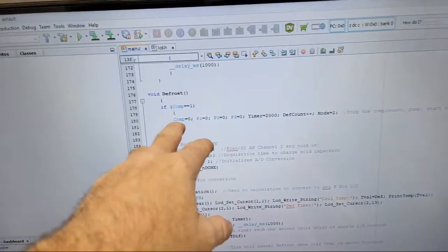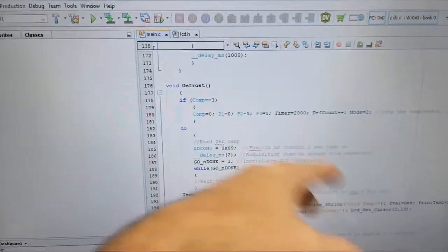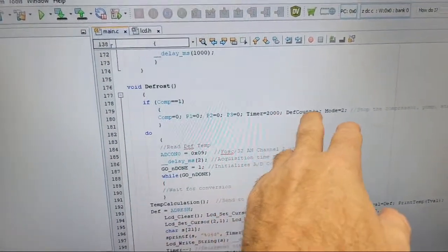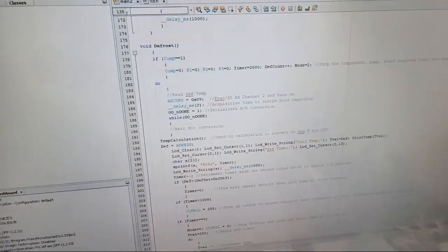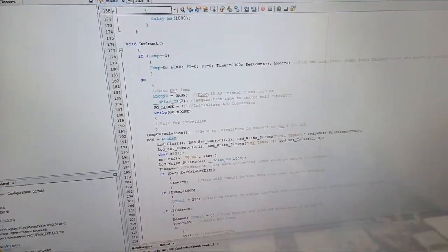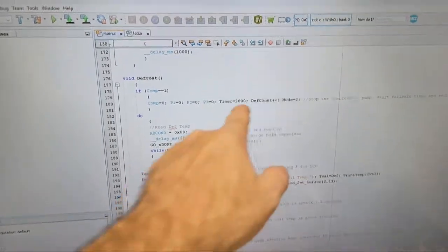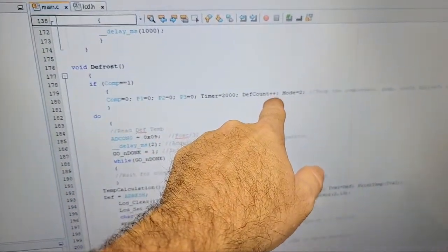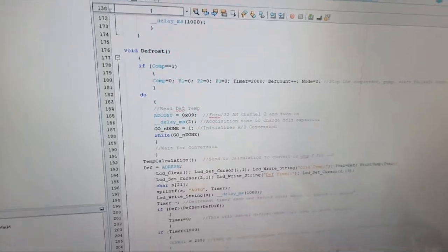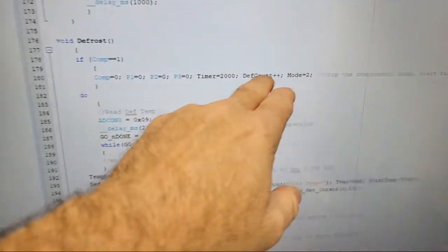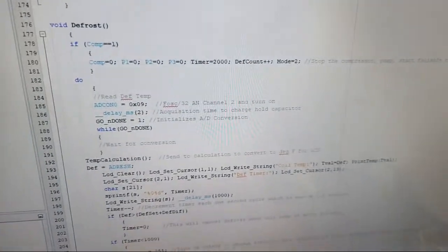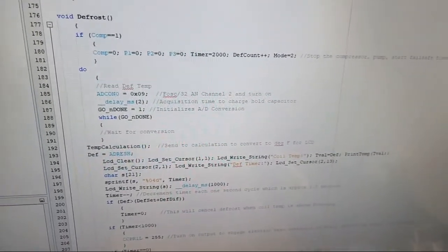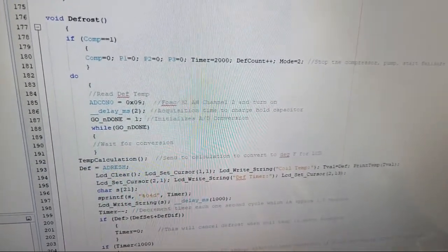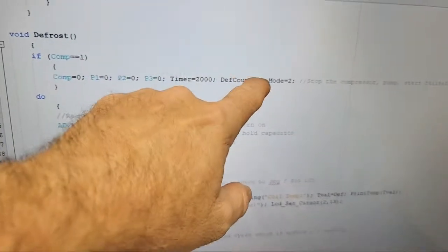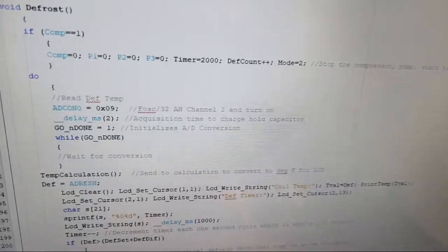It stops my compressor, pumps, or outputs will all be 0, and then starts a timer, and then it's going to start decrementing that. And DefCount? Oh yeah, that's just for my... I was like, what the heck is that? And I forgot I put that in there. There's another variable. I put it so I could go in there and push some button, and then look later on, see how many times my thing went into defrost. And every time it goes to a defrost, it just increments this counter variable. It's just something I could look at later.